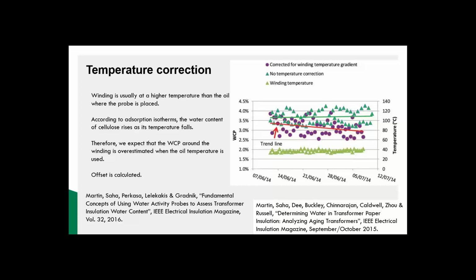So this allows us to do a recalculation from the probe, if we know what the temperature is around the winding. If we don't have any form of measurement, it could be looking at applying an IEC thermal model that would give us an idea of what the temperature is, and then we can adjust the water content. Again, we published all this, so if people want to know the algorithms and calculations and everything, then please do go and have a look.